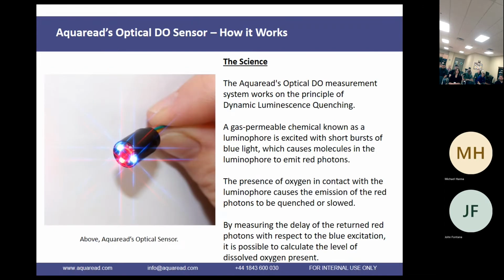Okay. So you can see on screen there, the DO sensor is lit up. If I was to plug this probe in, which I will do very quickly, you will start to see the LEDs flash, which I'll show you all in a second. Effectively, in the middle you've got a red disc. That's a photodetector, so that's reading information. The LEDs are used for the optics.